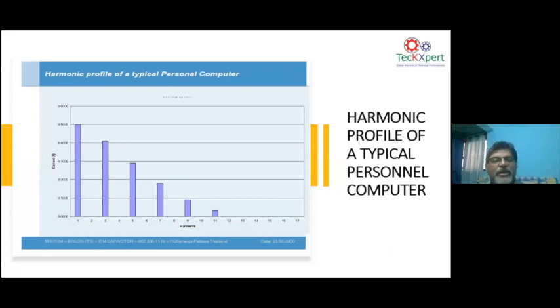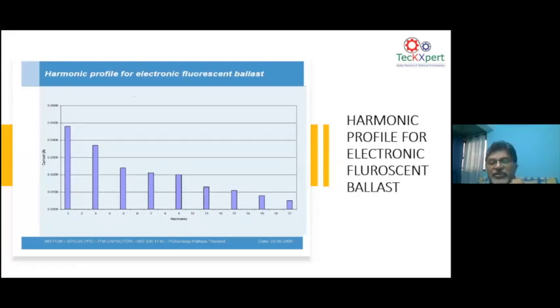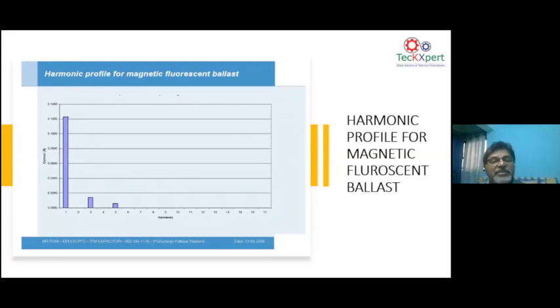Now, if you take a personal computer, since it's a single phase electronic load, it will start with the third harmonic current: 3, 5, 7, like that it goes on. Similarly, if you see an electronic ballast, which is used in a CFL, or an LED, it starts again with 3, 5, 7 because it's a single phase electronic load. A magnetic ballast is not supposed to produce any harmonics, but sometimes if the core of the ballast gets saturated, it can draw some amount of 3rd and 5th harmonic current. As aging takes place, the ballast also loses some of its linearity, so it can generate some amount of harmonics too.